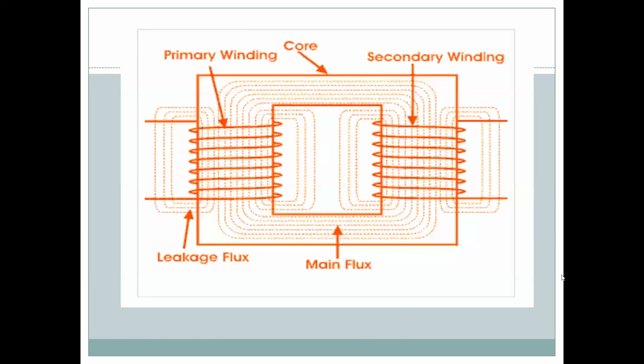Now that combination becomes this. So this is the steel frame. If you wind this wire and apply voltage over here, you will get more flux accumulation because of the low reluctance path, and it will induce more secondary voltage. So this way the transformer design has been developed. Fundamentally, it has been developed over here. So this is the basic fundamental design of a transformer, and you see not all the flux links to the secondary coil, and there is some leakage also. So that's why there is a loss in transformers.